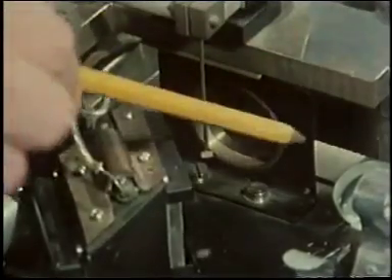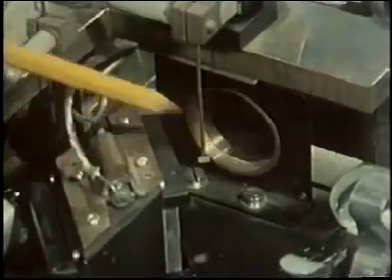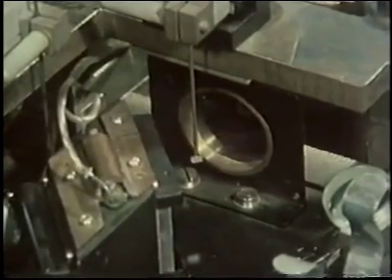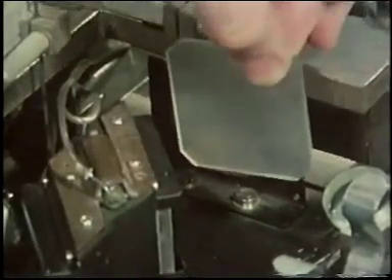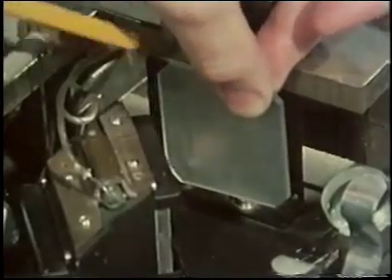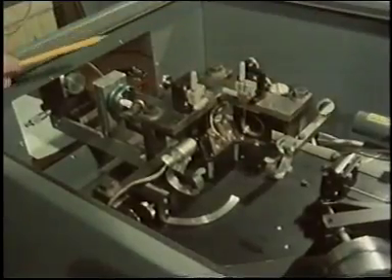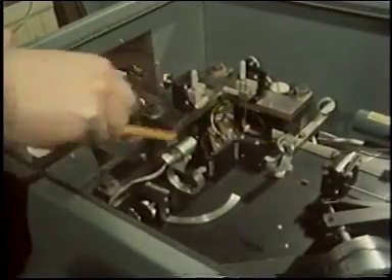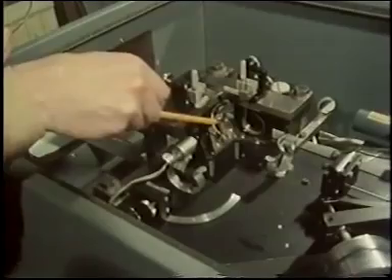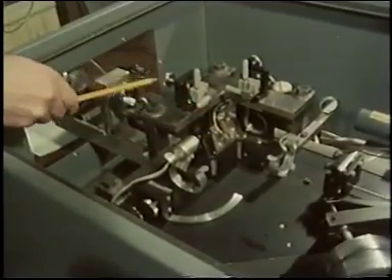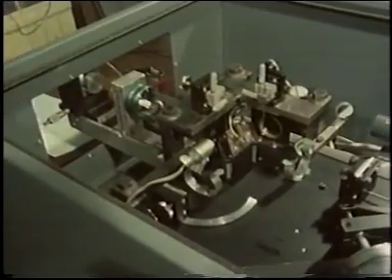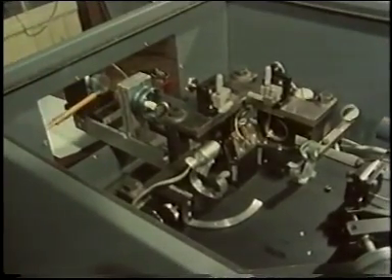The source down here produces radiation, which is collimated into a parallel beam by means of this lens here. The lens is made of germanium and is quite opaque to visible light, and if I put in this piece of ground glass, we see absolutely nothing on it. After the collimated radiation passes in the usual ways through the system, it comes down here, passes through our sample cell, and so to a radiation detector.